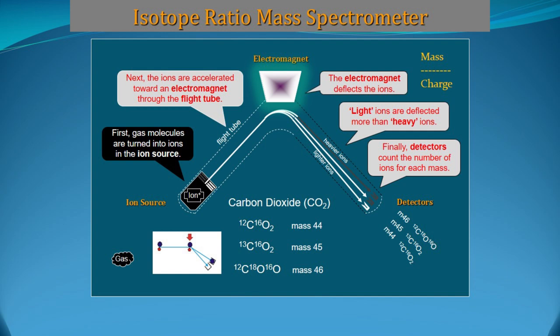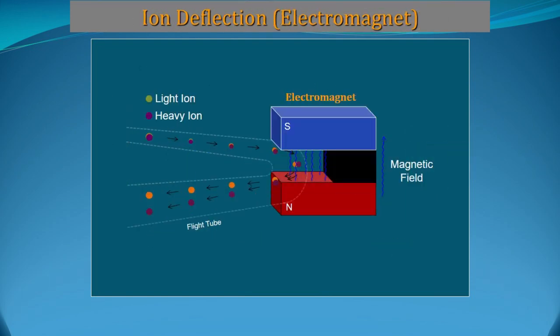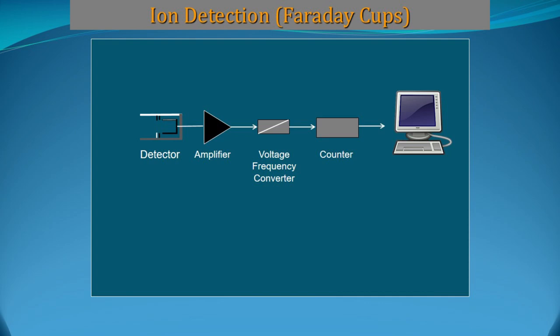In more detail, here at the left-hand side corner you can see the ionization chamber, which contains a tungsten filament that emits electrons. Sample gas enters into the ionization chamber and due to electron bombardment all the gas is converted into ions. Finally those ions enter the magnetic field in the form of a beam. As per their mass-to-charge ratios the ions separate and hit the detector, which is connected to an amplifier that amplifies the signals and transfers all these signals to the computer.